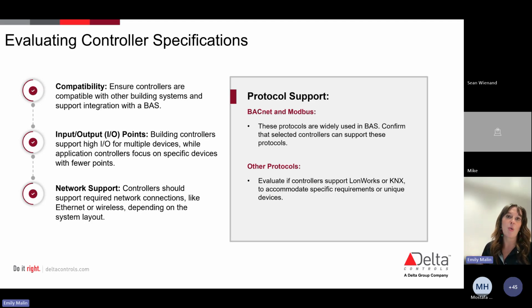And this is what I was talking about, where it really does start to vary from manufacturer to manufacturer. When you really start diving into the depths of controllers, it does get a little bit brand heavy, if you will. But the couple things to talk about, Moose took us through a few of these in BAS 102, right? So compatibility, network support, and protocol support. That's all going to be around how this controller is going to talk to the system as a whole, right? So how this system is going to interact with maybe what's already on the building or maybe those components that we're going to talk about next.